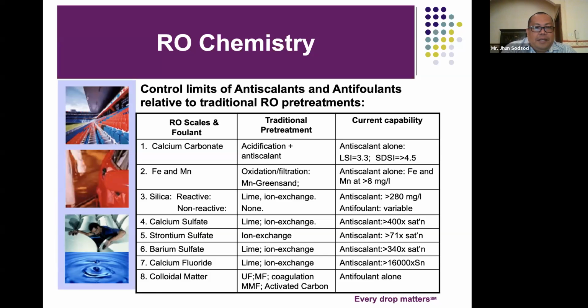Next is iron and manganese in the RO feed. The traditional treatment used is green sand. In our case, the antiscalant alone can already manage to handle iron and manganese even at greater than 8 ppm.